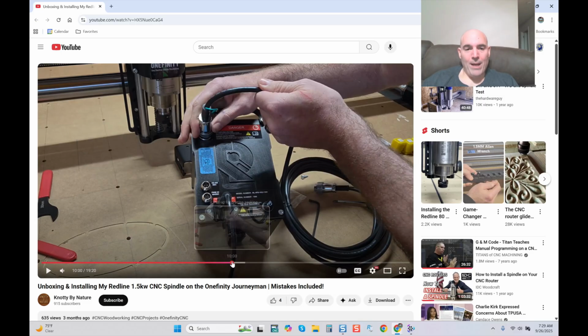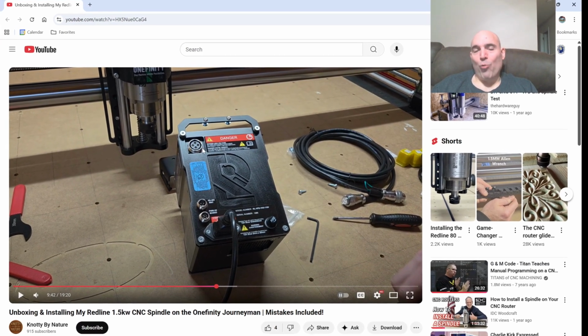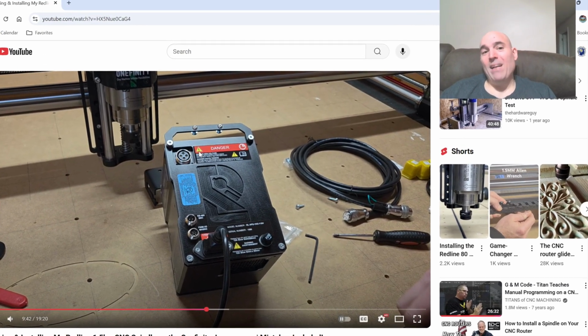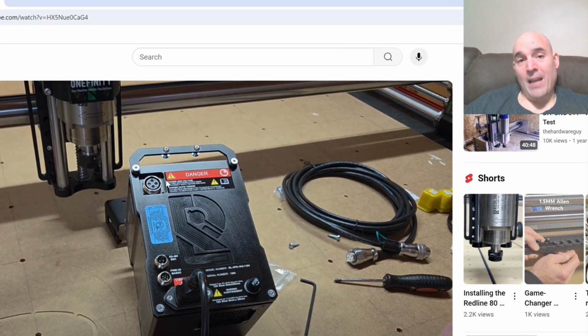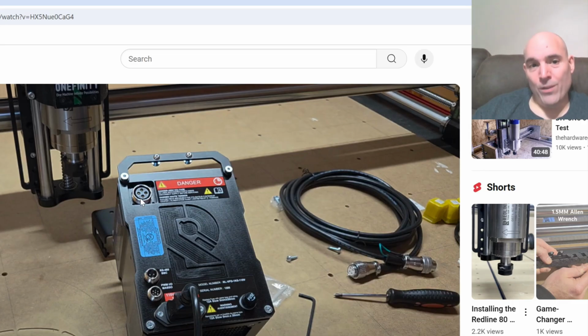And then on top of that, we have to make sure that the female plug, if we pull it back, is grounded on the opposite end, meaning inside the VFD enclosure, it would also have to be attached with a ground to this metal housing in order for this to be grounded. Why? Because we only have four pins.